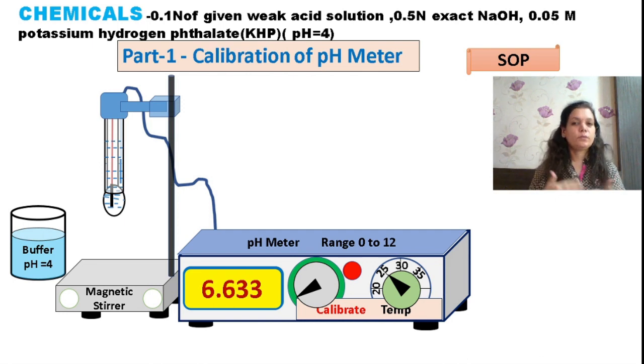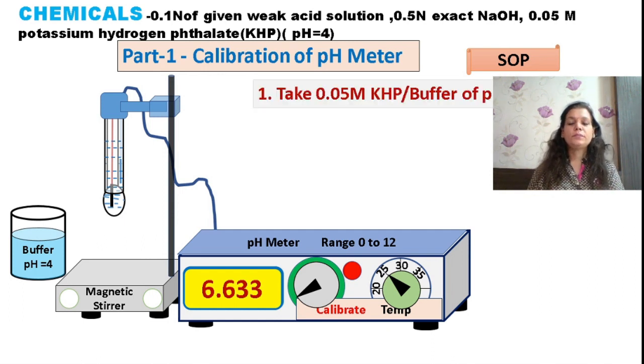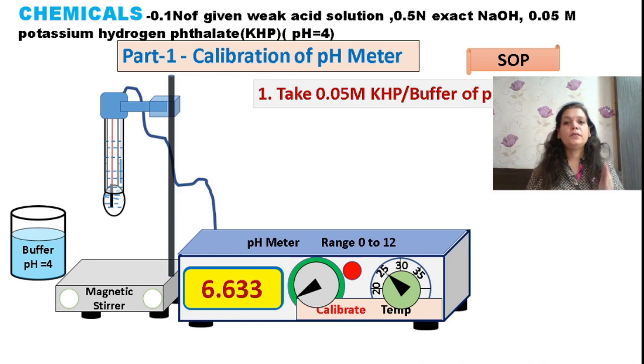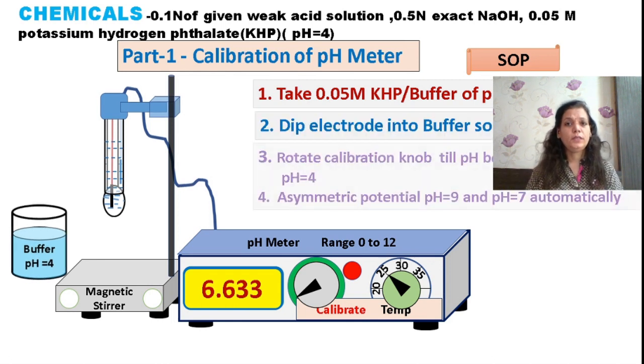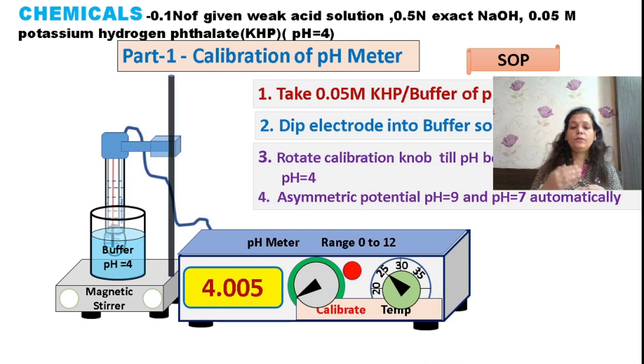To calibrate the pH meter, you can use standard buffer solutions of pH 4, 7, or 9 available in the market, or use 0.05 molar potassium hydrogen phthalate solution which gives a constant pH of 4. Dip your electrode in the buffer solution, measure the pH, and if it does not show the correct value, adjust using the calibration knob. When calibrating for pH 9 and 7, adjust the asymmetric potential developed by the glass electrode using the knob accordingly.